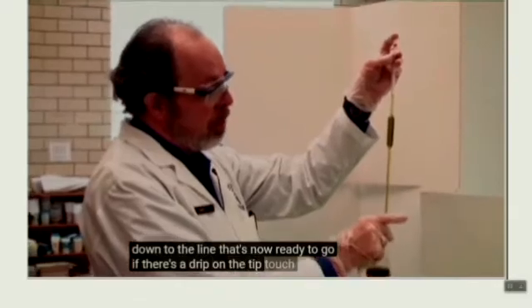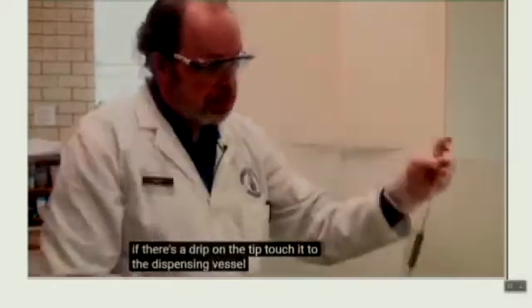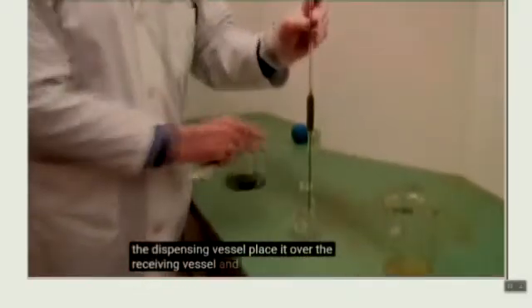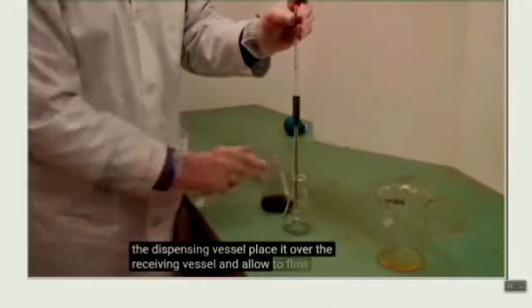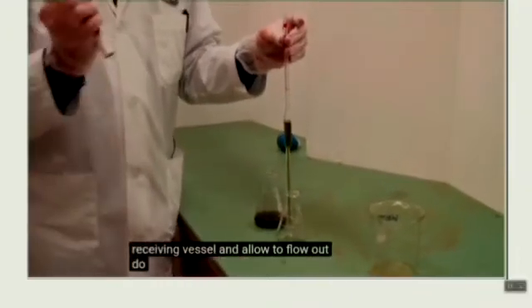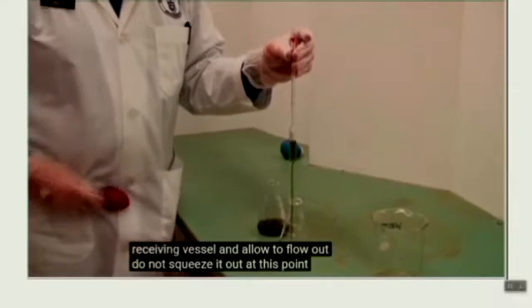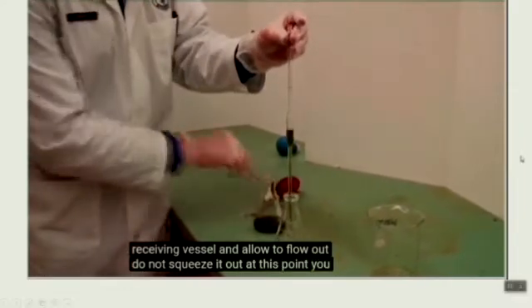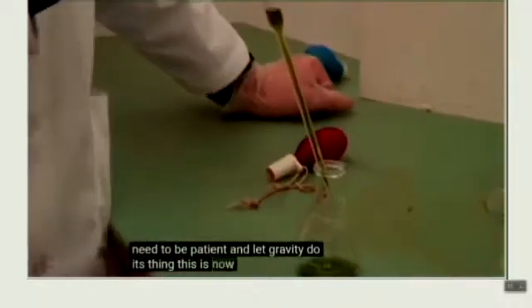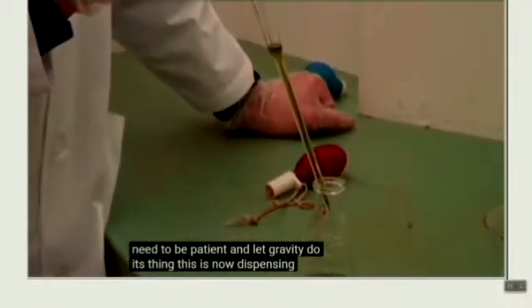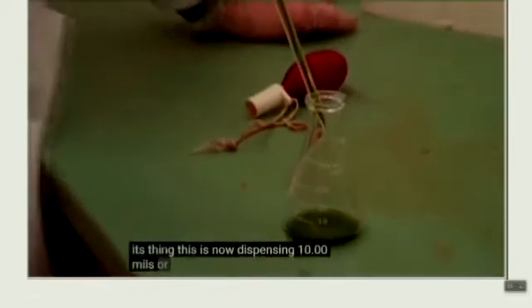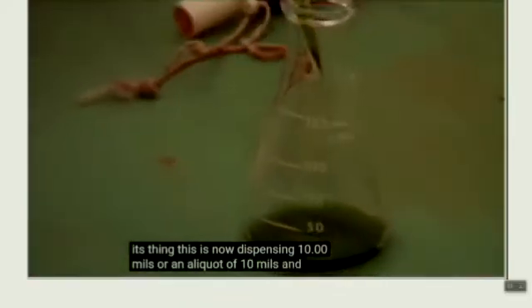If there's a drip on the tip, touch it to the dispensing vessel, place it over the receiving vessel, and allow to flow out. Do not squeeze it out at this point. You need to be patient and let gravity do its thing. This is now dispensing 10.00 mils, or an aliquot of 10 mils.